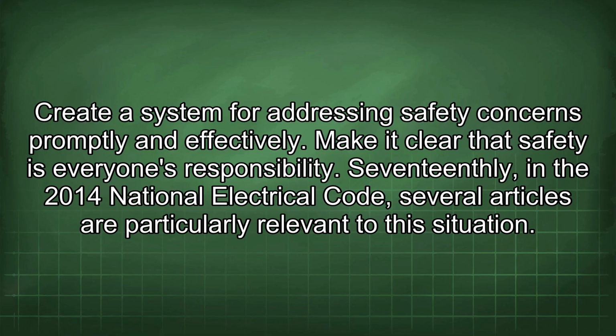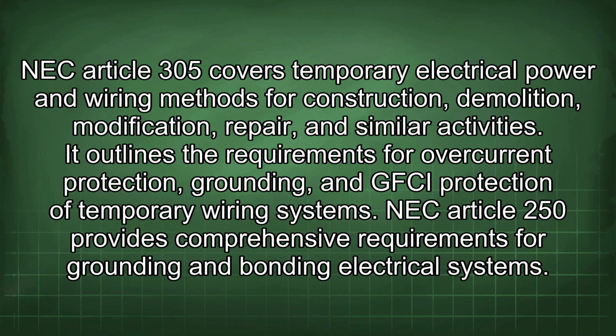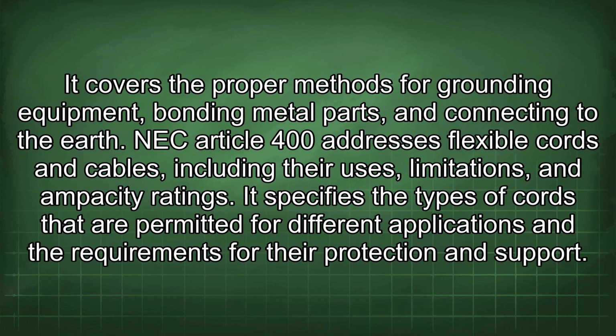17thly, in the 2014 National Electrical Code, several articles are particularly relevant to this situation. NEC Article 305 covers temporary electrical power and wiring methods for construction, demolition, modification, repair, and similar activities. It outlines the requirements for overcurrent protection, grounding, and GFCI protection of temporary wiring systems. NEC Article 250 provides comprehensive requirements for grounding and bonding electrical systems. It covers the proper methods for grounding equipment, bonding metal parts, and connecting to the earth.